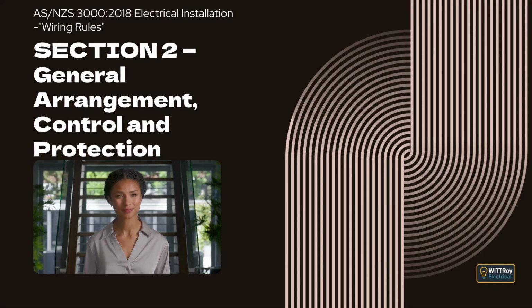In these cases, the wiring must be installed to minimize the risk of short circuit, must avoid locations that increase fire risk, and must still have short-circuit protection provided for the remainder of the circuit at the associated switchboard. Clause 2.5.5, protection against switchboard internal arcing fault currents.